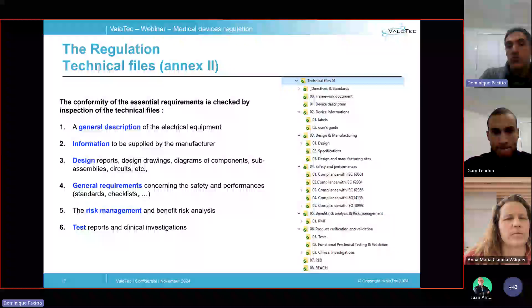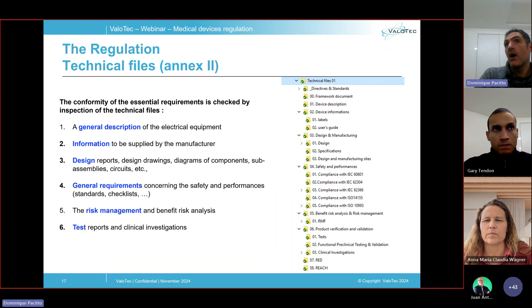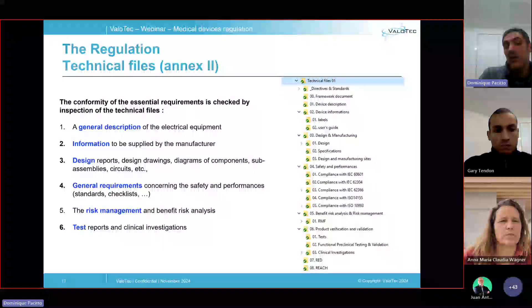The second part is related to the information provided to the users, for example, the labelings or the user's guide. The third part is related to the design and includes design drawings, design reports, specification, diagram of components, circuit, subassembly, etc. The fourth part is related to the safety performances and includes tests and proofs of the conformity relative to the regulation. For example, test certificates from a certified body. The part 5 is related to the risk management, and the part 6 related to the tests. Technical tests you can perform at your office to provide evidence that your device works as expected, tests on animals and clinical tests on human beings.